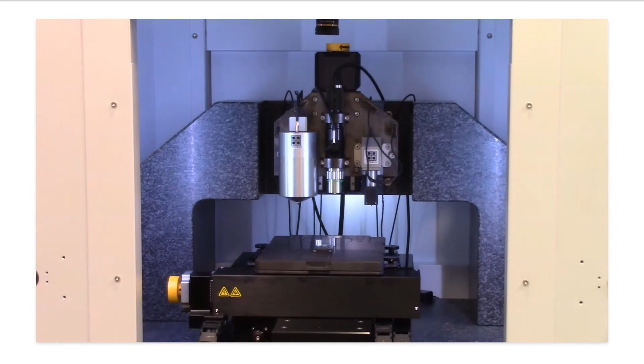Currently, it is set up in a two transducer or dual head mode. On the left, we see a 3D OmniProbe, and on the right, we see a nanoDMA 4 transducer with piezo scanner. We can use the higher force 3D OmniProbe for deep indents and scratches, and then SPM it using the low load transducer setup.